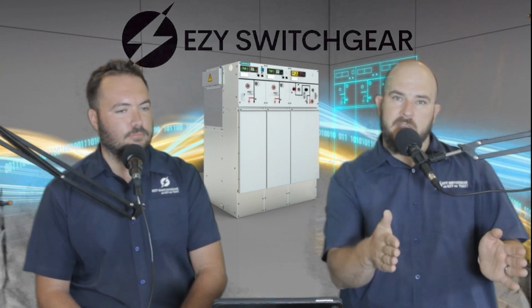Okay, great. So Eben, I need MV Switchgear. Where do I start? Okay, so firstly, you need to understand what load are you going to feed. Is it going to be a mini sub? Is it going to be a primary sub? Is it going to be some sort of a mill or something with rotational loads? What is the fault rating of that sub, of that line, of the feeding line? And then obviously what is the application? So there would be primary switchgear applications and there would be secondary switchgear applications. And then on top of that, there's also the protection, the kind of protection that you need to take into account. So all of those things are important.